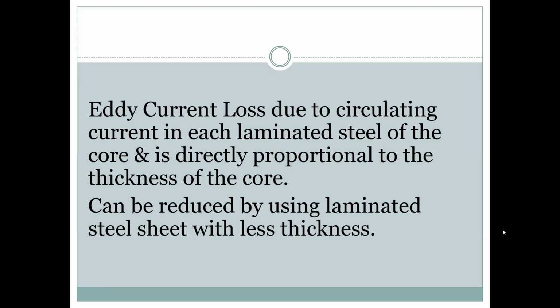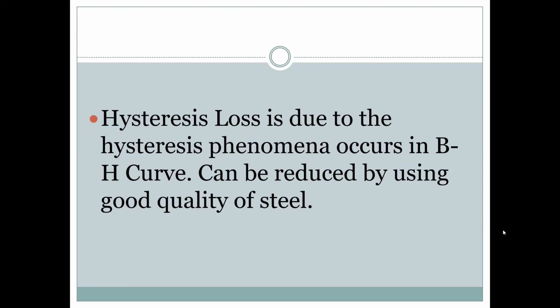Eddy current loss is due to circulating current in each lamination of the steel for the core, and is directly proportional to the thickness of the core. So to reduce the eddy current loss, we reduce the thickness of the core sheet, which is 0.27 millimeter; we keep it like that. It can be reduced by laminated sheet steel with less thickness, whatever is possible. But if you keep on reducing the thickness, it may not be solid enough to hold the winding. So we have to keep that in mind. So it is an optimum level, 0.27 millimeter thickness, we keep it like that.